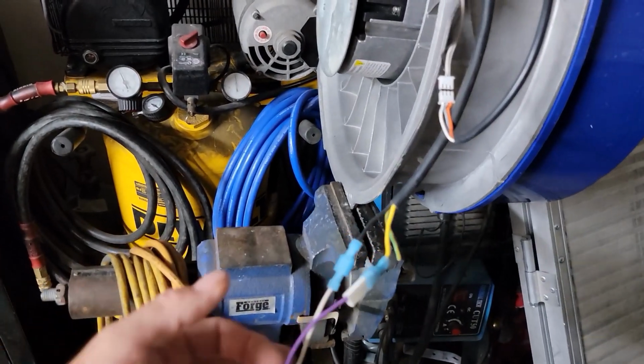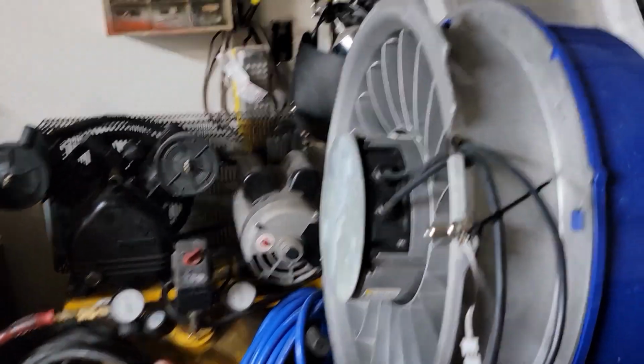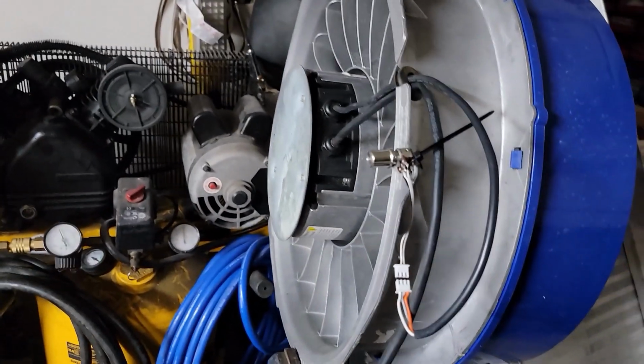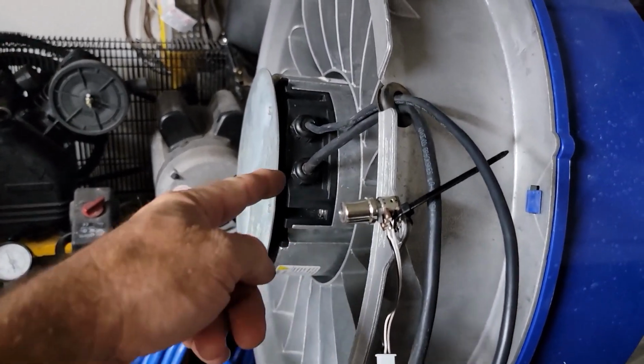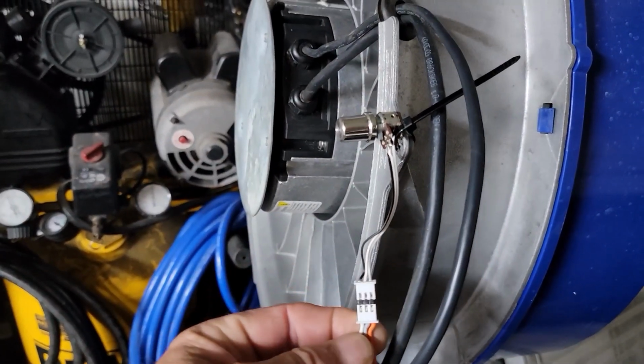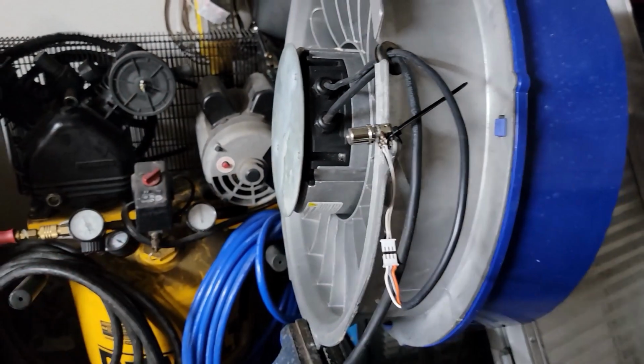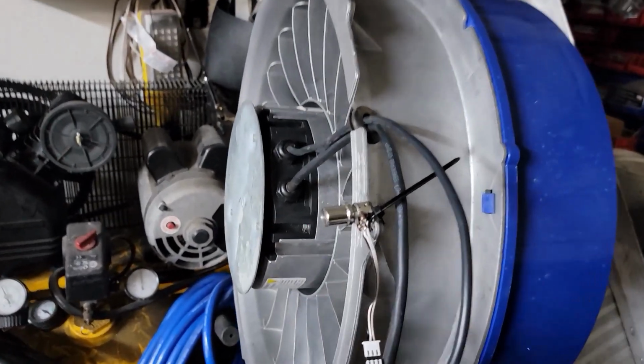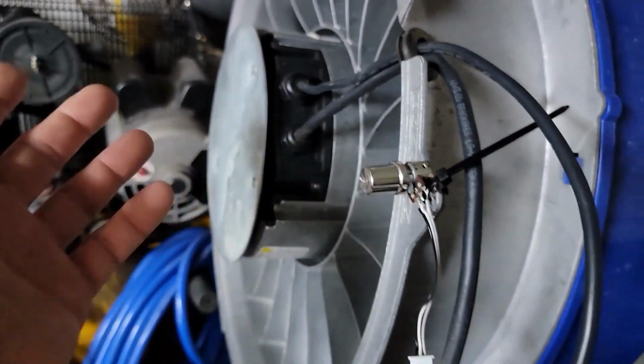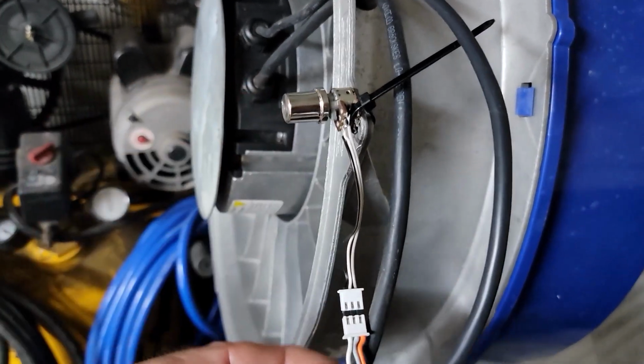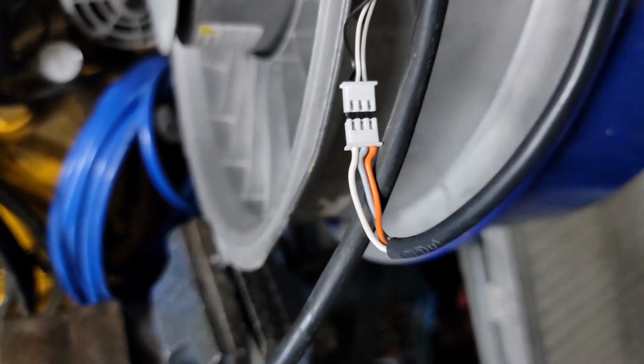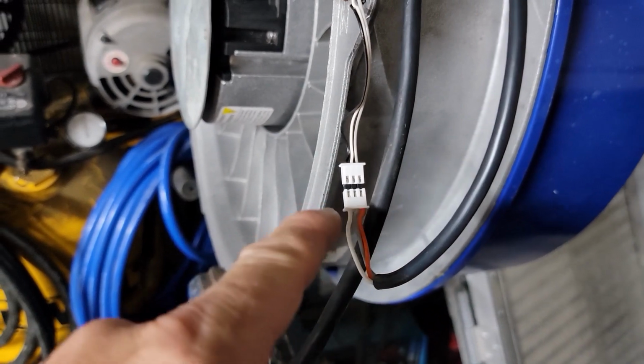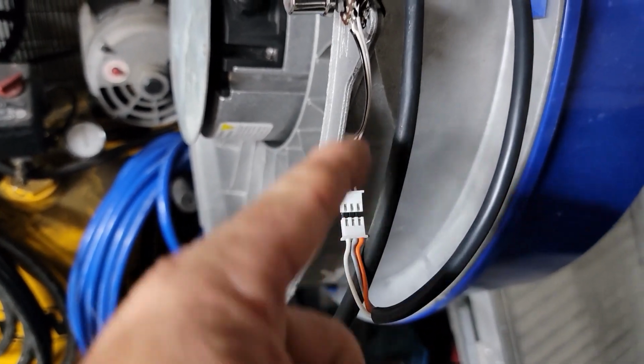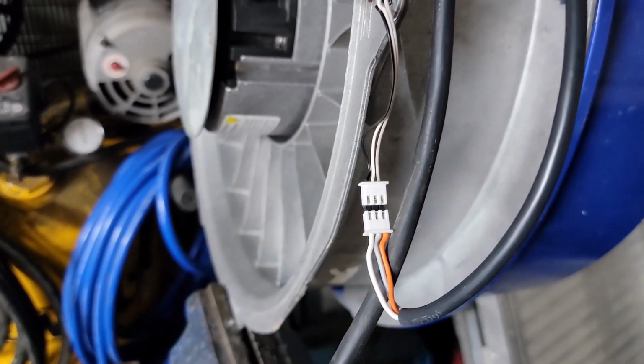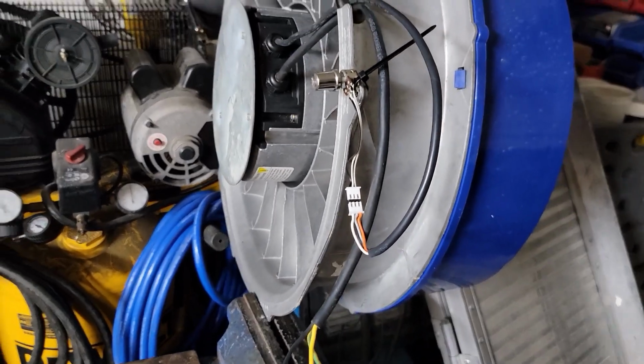It is a high voltage input, basically an ECM motor. It has its own 10-volt power supply built in that it produces, and then you send a 2 to 10 volt speed reference command into it to run the motor. Right now I just have a potentiometer. On these motors, orange is 10 volts, white is your common, and gray is the voltage going back in to tell it what speed to run.